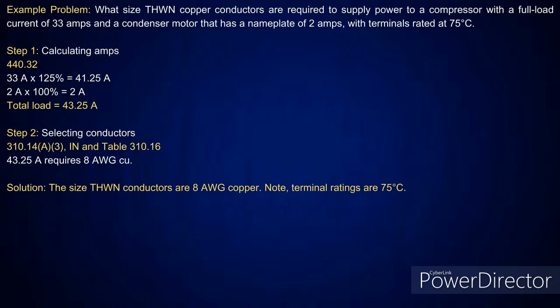But the same principle happens here. You're going to take the largest at 125%, and all other motors are added at 100%. Looking at 440.32, we take the 33 amps at 125%, which gives me 41.25 amps. Then I add the 2 amp condenser, which gives me 43.25 amps. Then I go to table 310.16, pick up the 75-degree column. The next size above that is 50 amps, which is a number 8 conductor.